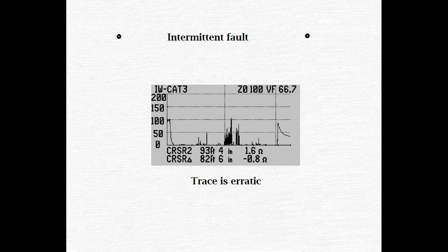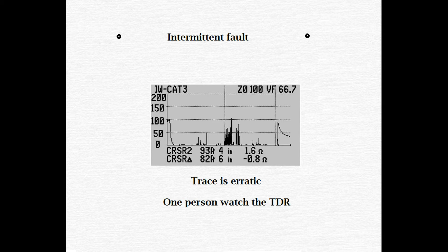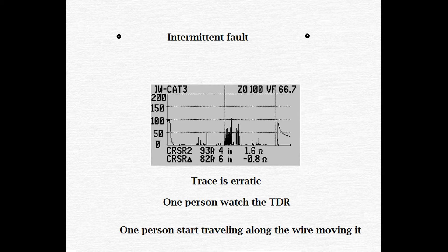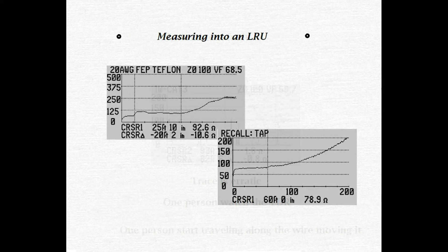Here we see a technician's worst nightmare, an intermittent fault. With the TDR, each time it sends out a pulse can be changing, which will result in an erratic trace. To troubleshoot this one, enlist the help of another person to watch the TDR. While you travel along the wire moving it, eventually you'll find the spot that's causing the erratic reading.